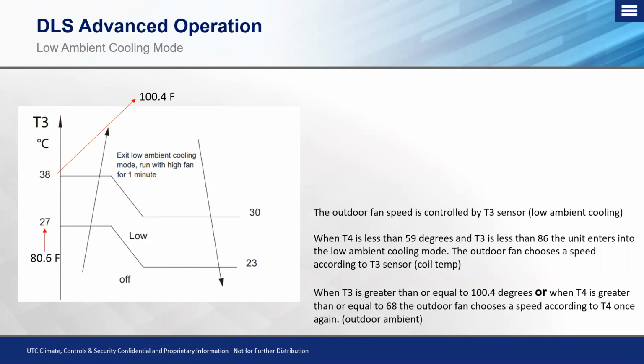The outdoor fan in this low ambient cooling mode now chooses a speed according to that T3 sensor, or the coil temperature sensor, because now we need to take the temperature off that coil to modulate the fan speed, to get proper head pressure control. Essentially, it's acting like a motor master control.